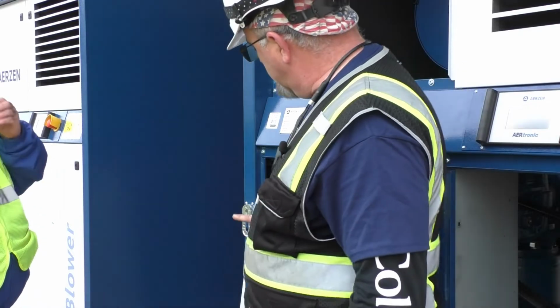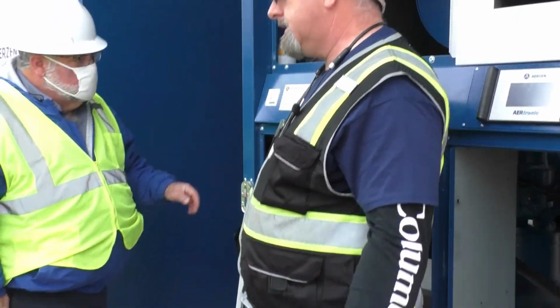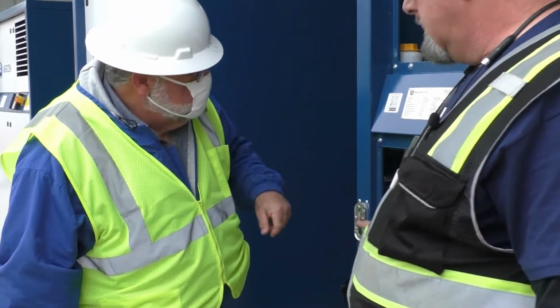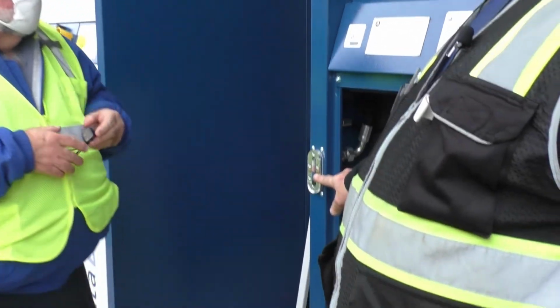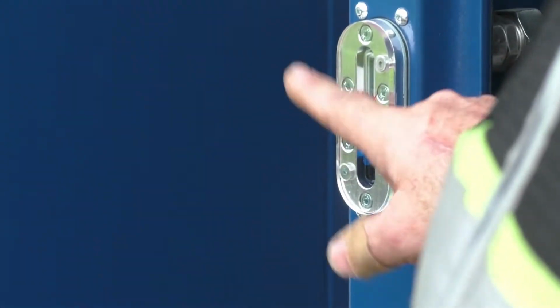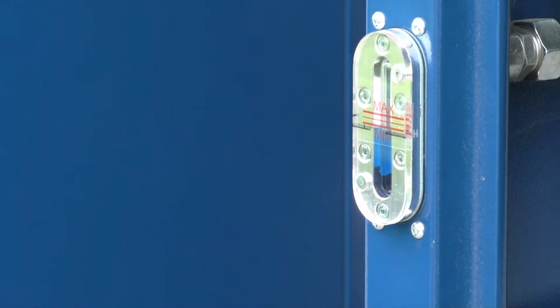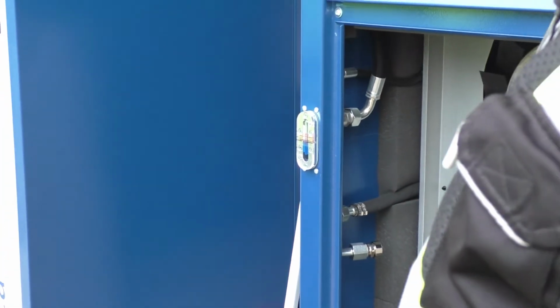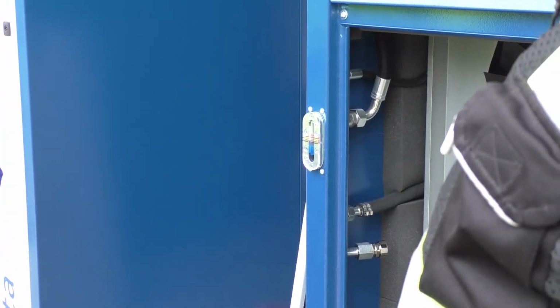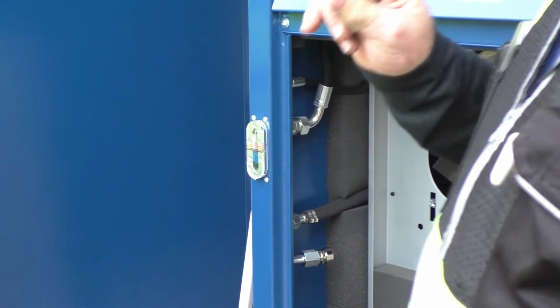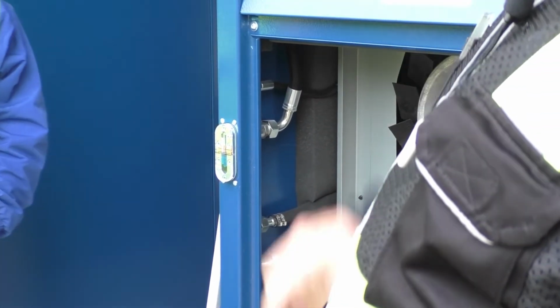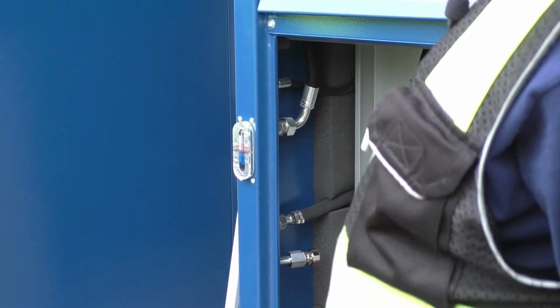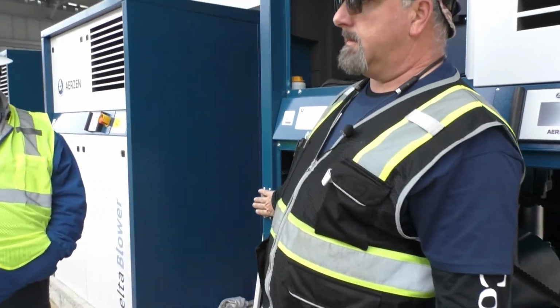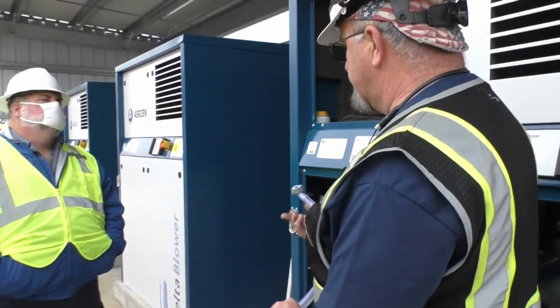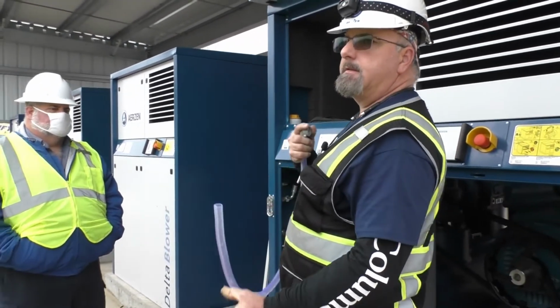So doing your visual check, usually if you're just even walking by, you can glance at this and that'll let you know what your oil level is. I have not adjusted the ones on here that need adjusting yet, so they don't match what's on the stage. All of the stages are set at the dot or touching it one side or the other. But that's where a quick reference. If you have any doubts whether or not this is right, I will show you on the stage where you can find those sight glasses to verify.